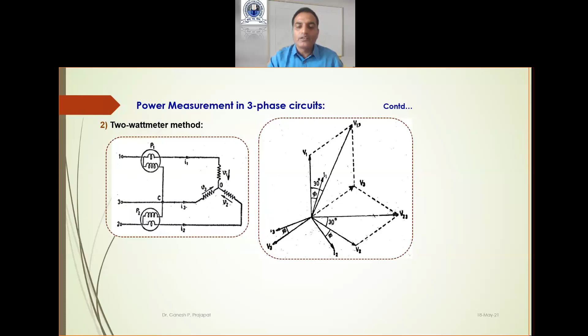So I think we should end here because this topic is quite long. We have seen here that the sum of the readings of these two wattmeters will give the total active power consumed by this three phase load. But if you want to measure the reactive power as well as the power factor of this load with the help of these two wattmeter readings, that is also possible with this two wattmeter method. The measurement of reactive power and the power factor with the help of these two wattmeter readings we will see in the next class, that is tomorrow's class.